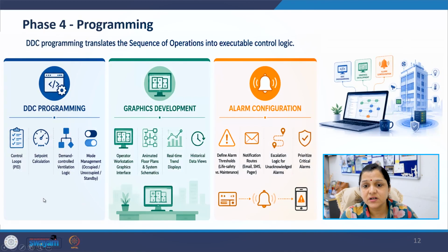And the fourth phase is programming. During the programming phase, the sequence of operations is converted into actual control logic. This includes PID control loops, scheduling logic, set point calculation, economizer sequences, and occupancy modes. Graphic development is also performed. Operators require user-friendly dashboards with floor plans, schematics, alarms, and trend displays.